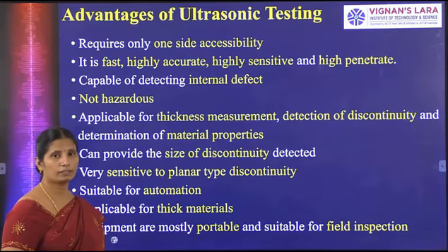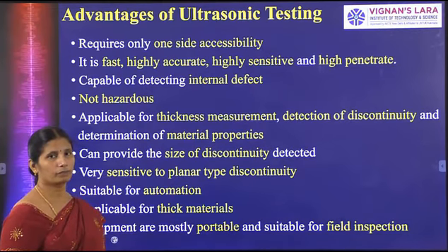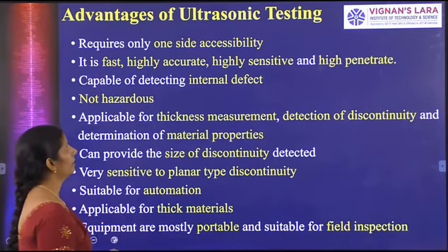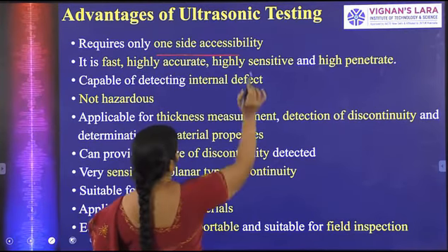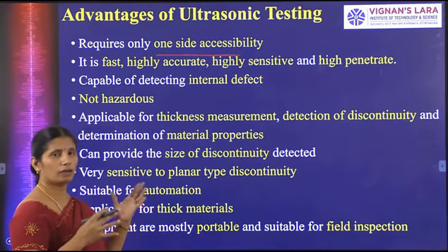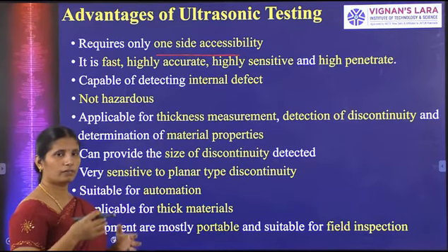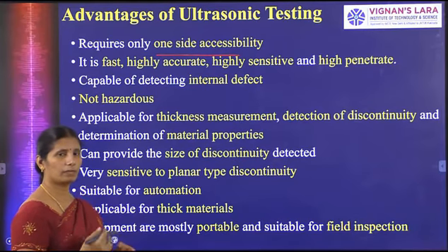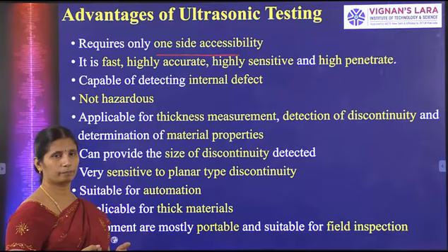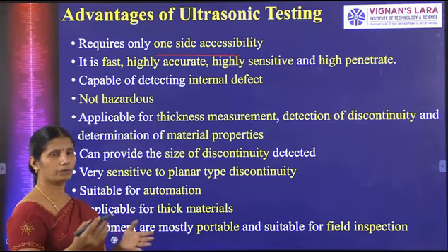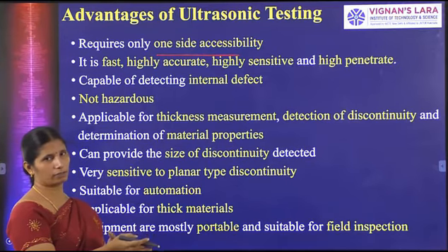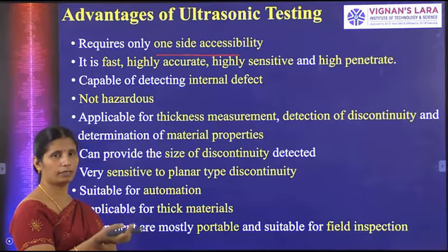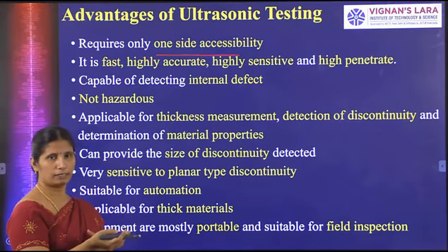So up to now we have discussed ultrasonic testing. What are the advantages of ultrasonic testing methods? It requires only one-side accessibility. That means if there is a large product, we can pass the ultrasonic waves from one side. No need to handle that material from both sides. From one side only we can pass the ultrasonic waves and find the thickness of that material as well as the defects present in the material.